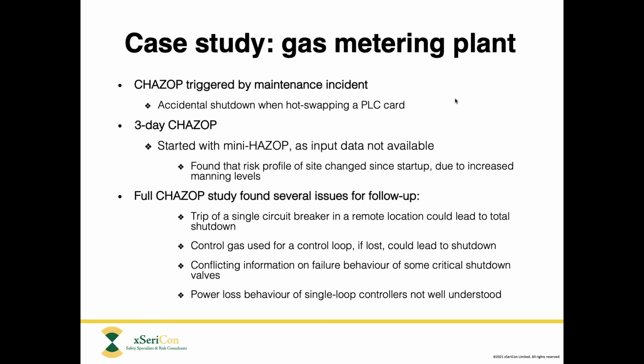There were quite a number of other issues that we found as well. And some of them were that the system was not as well understood. They were lacking some information on how the system would behave in certain upset scenarios. So all in all, very interesting, and I think a very worthwhile CHAZOP study there for really relatively little cost.